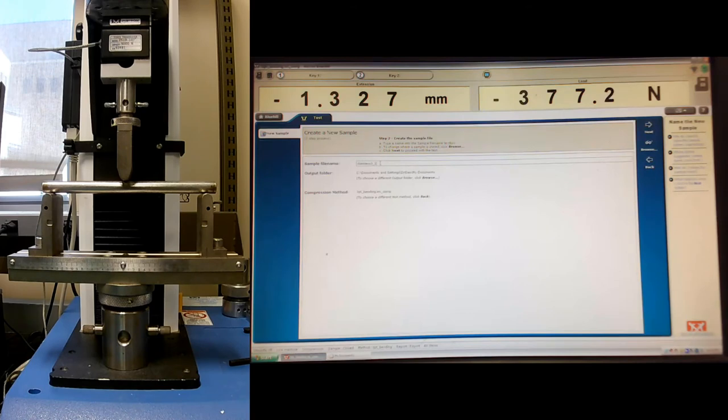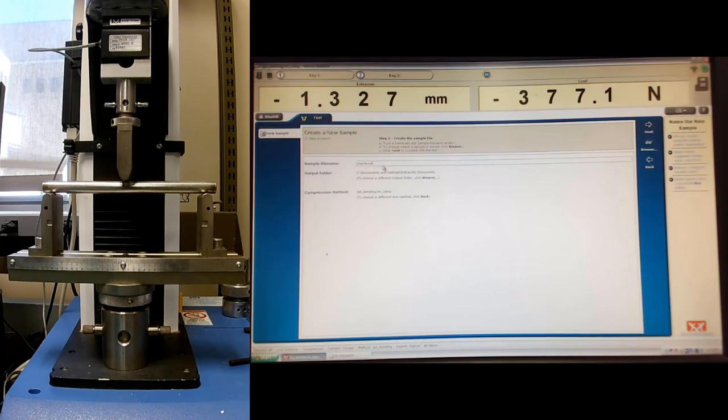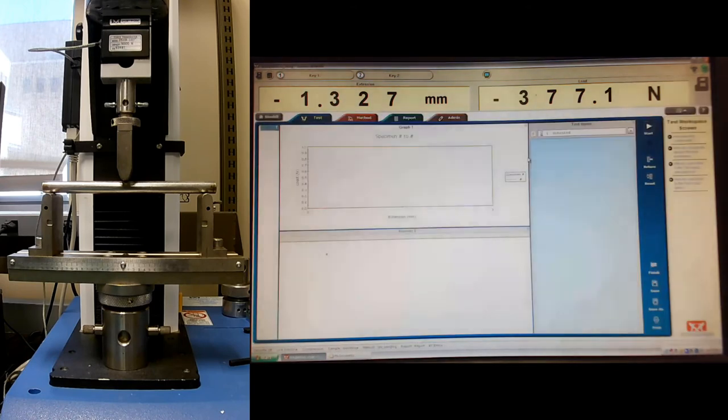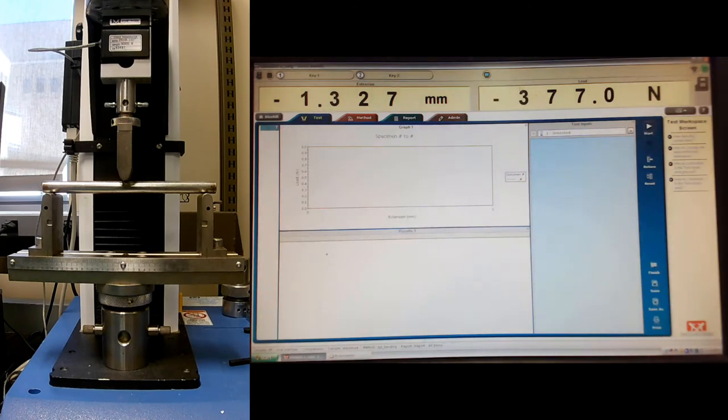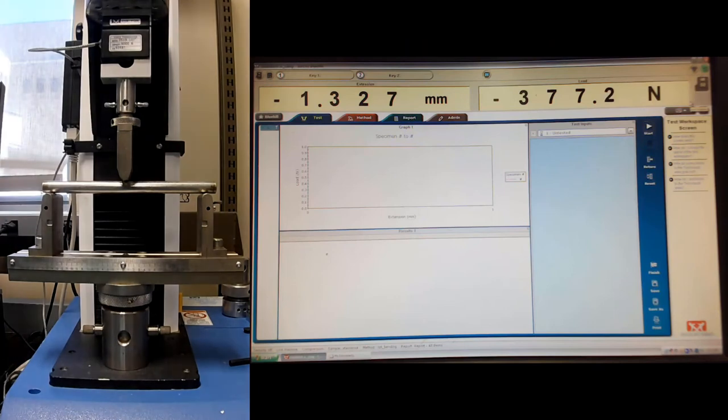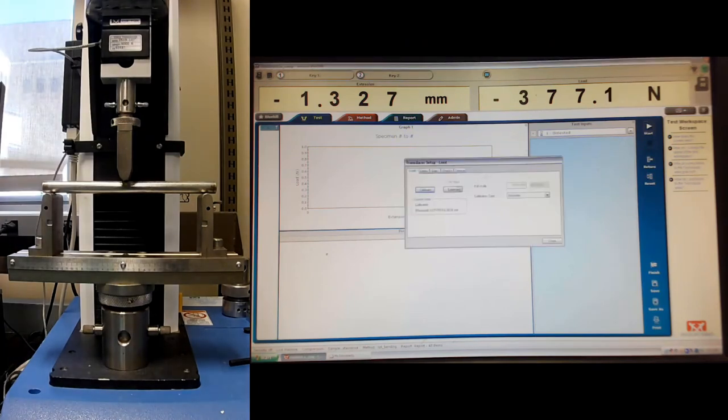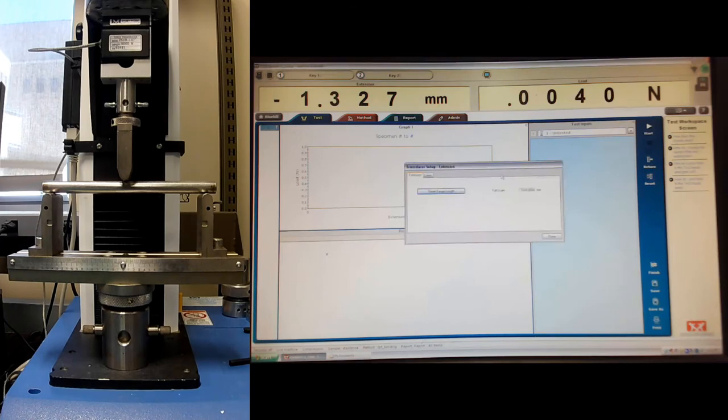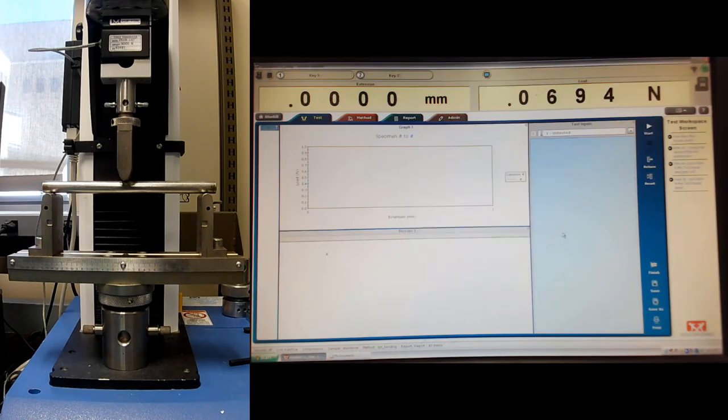Okay, this is actually my fourth stainless steel sample. I've already tested a couple to make sure they would work. But I wanted to show you one just to prove to you that it also worked. So now I just want to go ahead and make sure this is in here well. I'm going to reset the gauge length, balance the load cell to zero so we start out at zero, zero. And we'll go ahead and start the test.